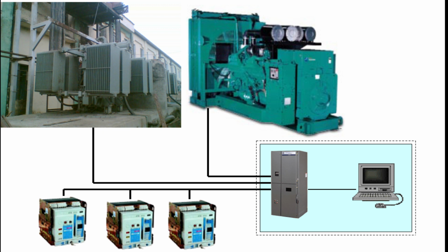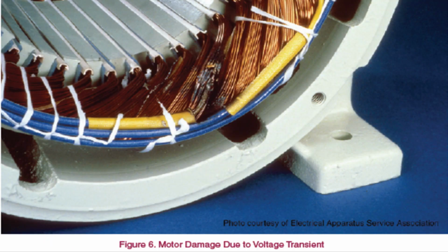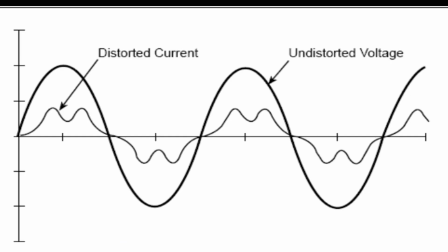Do you think 6% voltage distortion and 6% current distortion have the same adverse effects on an AC power system? False. 6% voltage distortion on a general use bus will likely cause equipment misoperation and other problems, while a 6% current distortion may not.